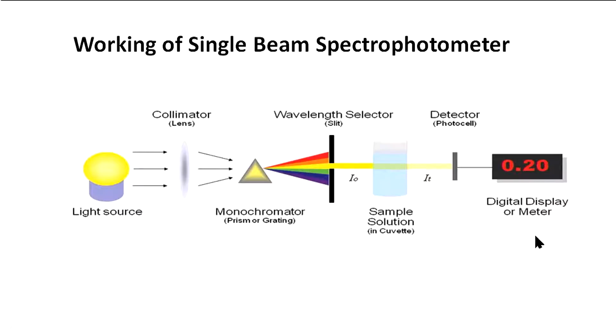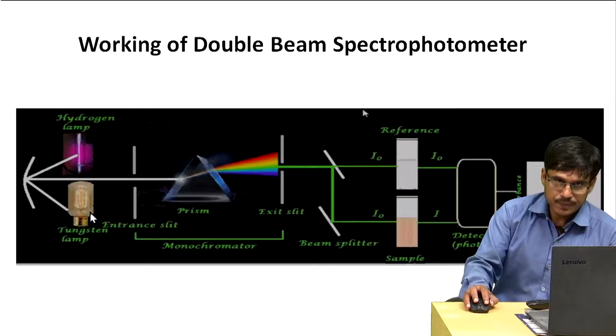This is the other scheme, for the double beam spectrophotometer. Here again you can see at the left a light source, a hydrogen lamp or tungsten lamp. Then there is another setup known as a monochromator. A monochromator is a setup of two slits, in between which there is a prism or grating. First the light passes through the left slit and strikes the prism. It splits the light into 7 colors, which then pass through the exit slit.